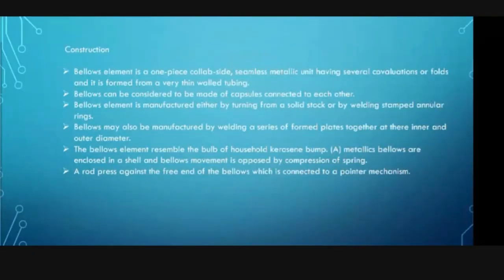Next. So here is the construction. The bellows element is a thin, collapsible, seamless metallic unit having several convolutions or folds, and it is formed from a very thin wall tubing. Bellows can be considered to be made of capsules connected to each other. The bellows element is manufactured by turning from a solid stock or by welding stamped annular rings. Bellows may also be manufactured by welding a series of formed plates together at their inner and outer diameter. The bellows elements resemble the bulb of a household kerosene pump. Metallic bellows are enclosed in a shell, and bellows movement is opposed by compression of a spring. A rod presses against the free end of the bellows, which is connected to a pointer mechanism.